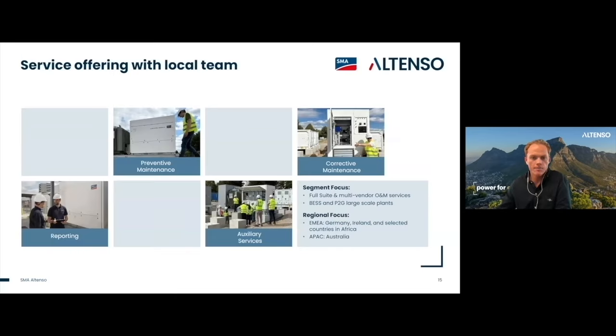So just one other point, I mentioned that we would come on board as a technical partner for the project in terms of the design and supply of the equipment. We would also offer a full suite of multi-vendor O&M services for PV and BESS applications, and have a local service team here in South Africa and other service partners throughout Africa. And we'll also be able to walk through the design life of the system you require from the beginning, factoring different round trip efficiency and state of health considerations related to the battery, and essentially address the problem that you're trying to solve from the onset. And we're also happy to provide a high-level techno-commercial analysis on the return on investment you might be able to expect integrating renewable energy and BESS into your system.